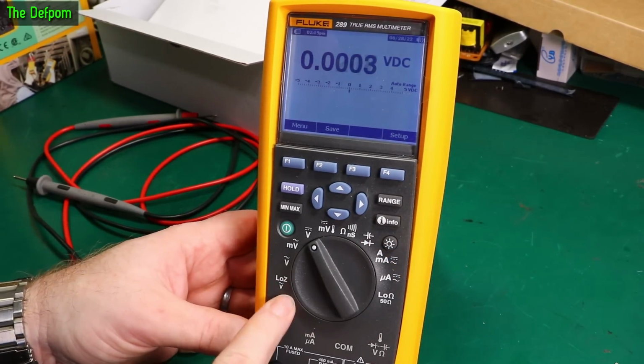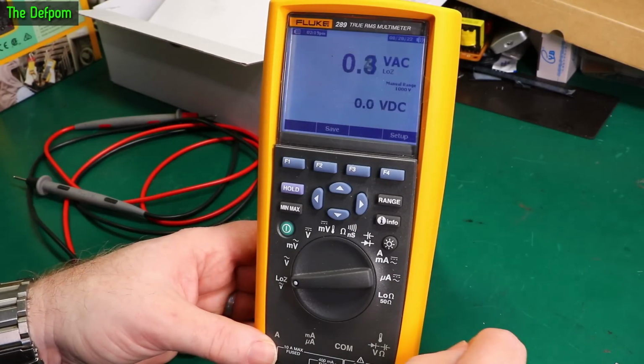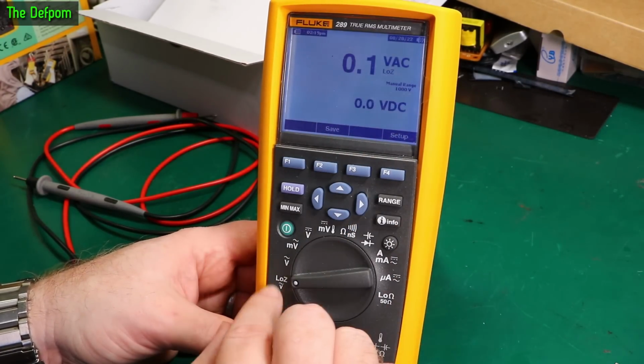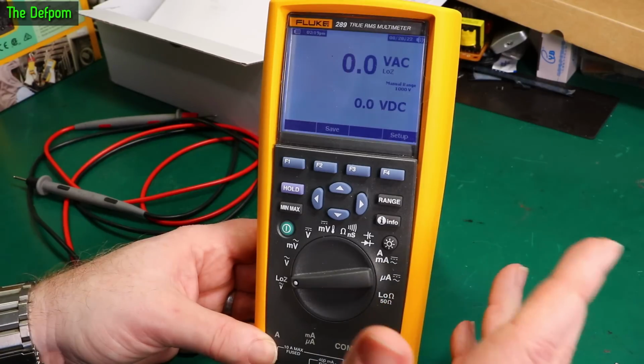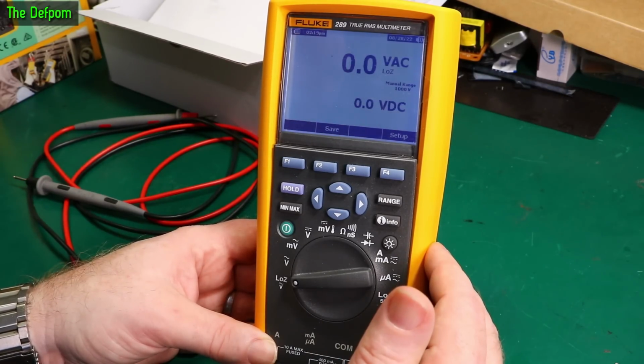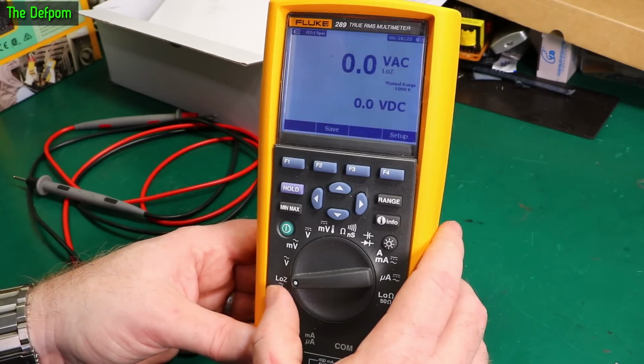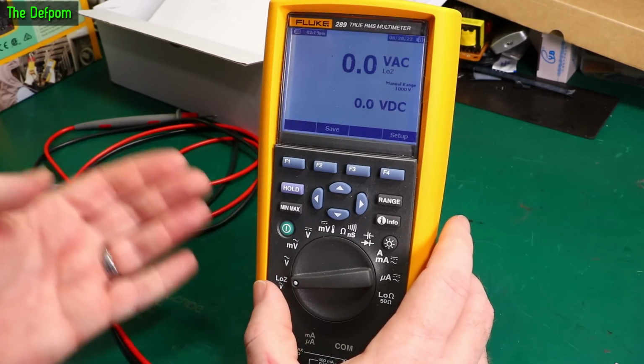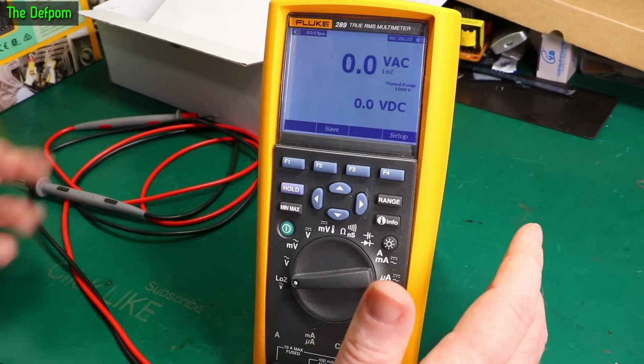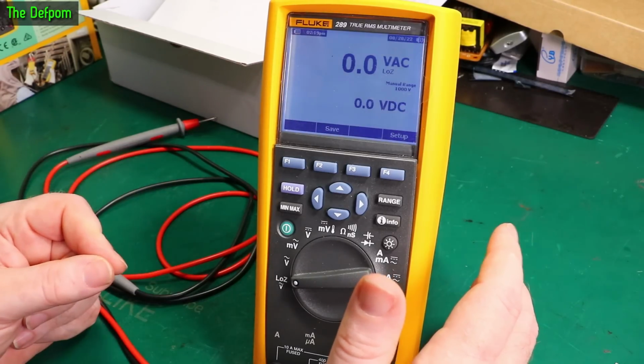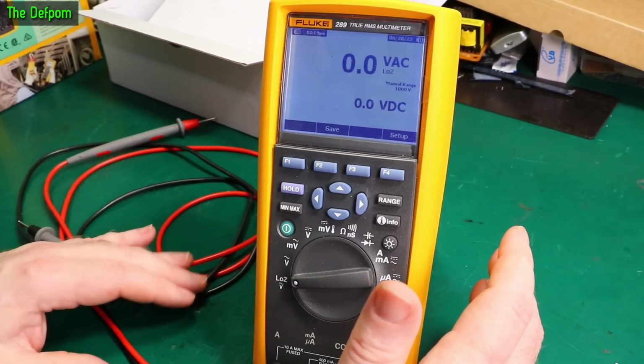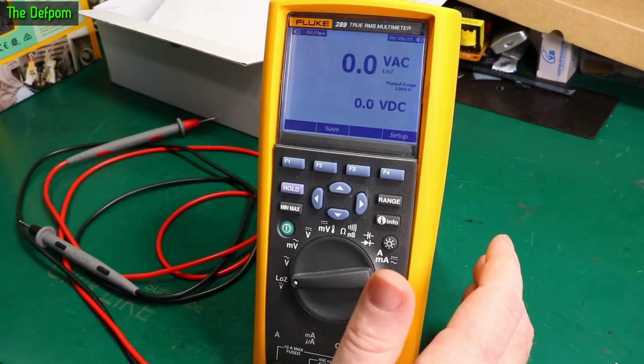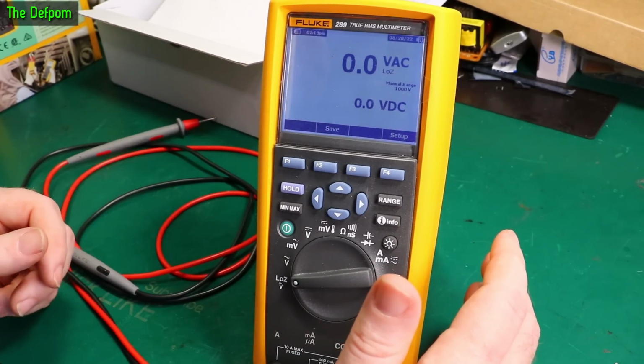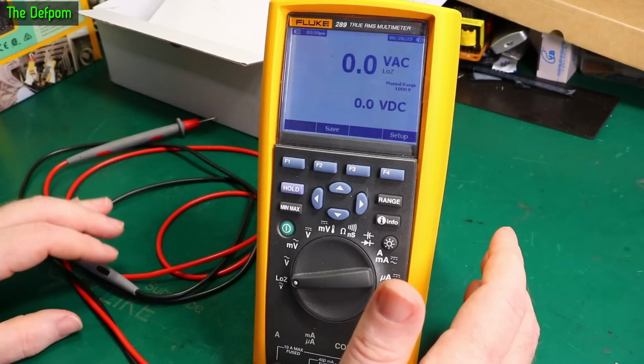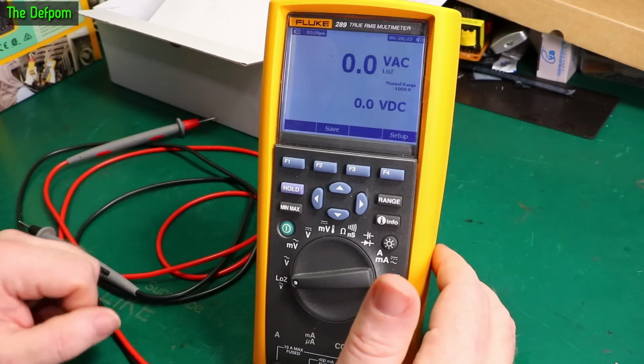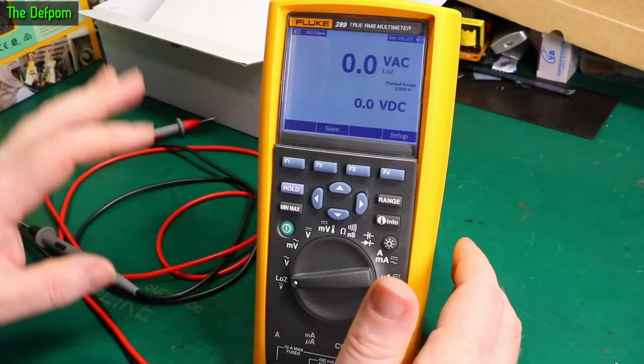So let's start on low Z and see what this does. It's volts AC, low Z for volts AC because it's AC only, and this is the voltage reading. It gives a loading across the supply to discharge capacitors and stuff like that, I suppose. Main thing is so you don't get stray voltage readings. If you're doing mains AC work, household stuff, you can pick up stray voltages induced in the cables from another cable. You may be reading 60 or 70 volts in a cable, for example, but that isn't actually there - it's purely being induced by its proximity to other cables. So the low Z reading puts a bit more loading on the line and helps kill any of those false readings.